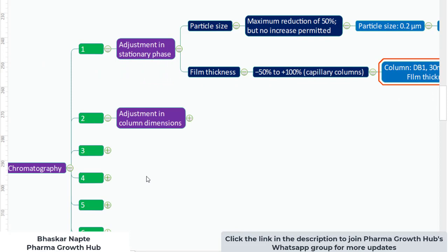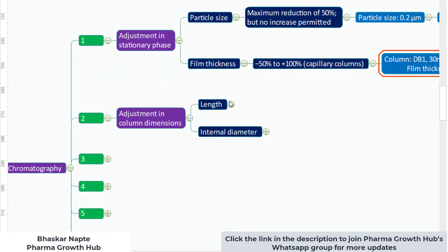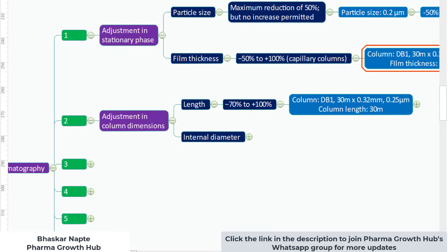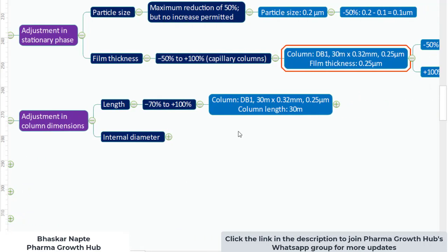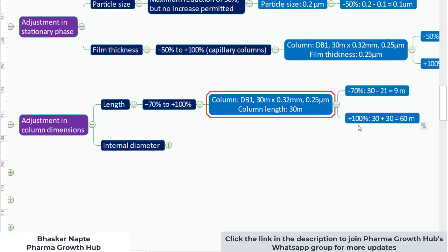The next point is adjustment in column dimensions. The length of the column can be changed by minus 70% to plus 100%. For a 30-meter column, minus 70% gives 9 meters, and plus 100% gives 60 meters. So if your column length is 30 meters, you can use a column from 9 meters to 60 meters, and this change is accepted according to USP general chapter 621.